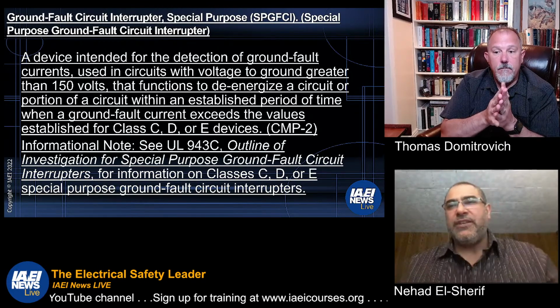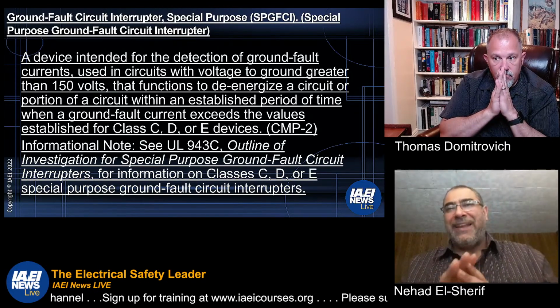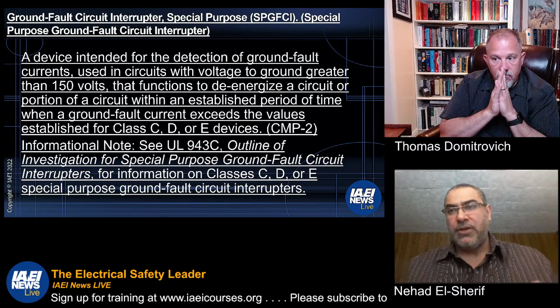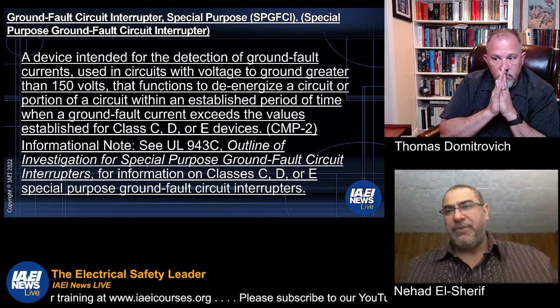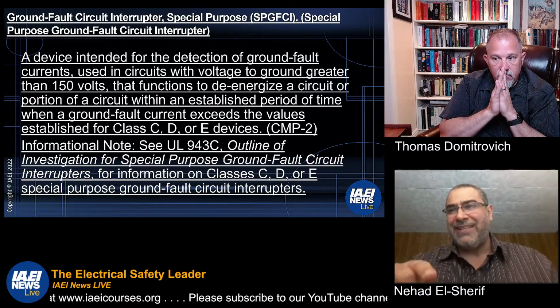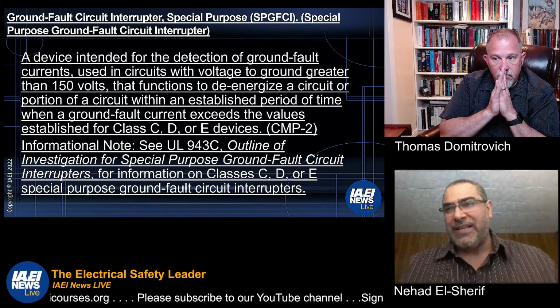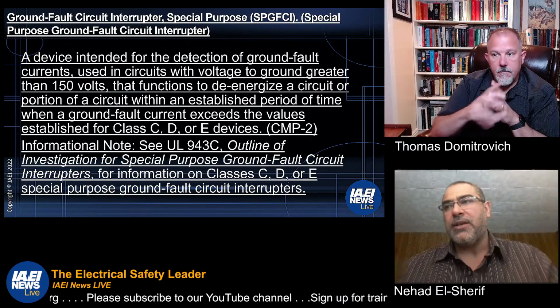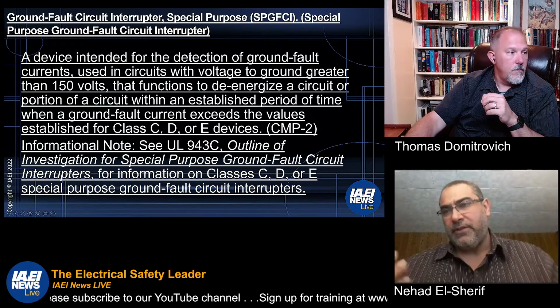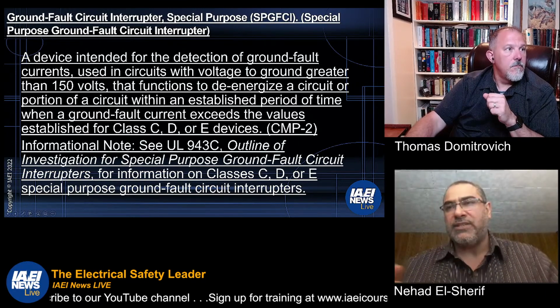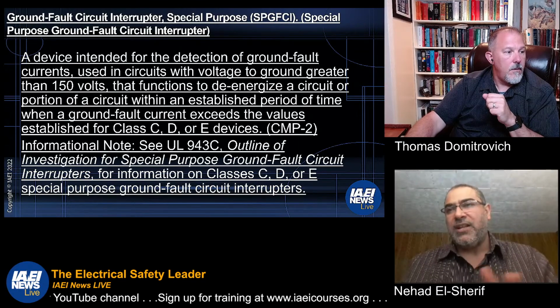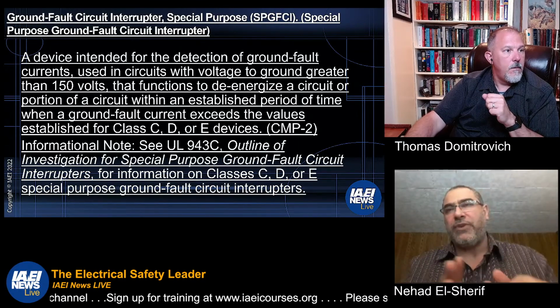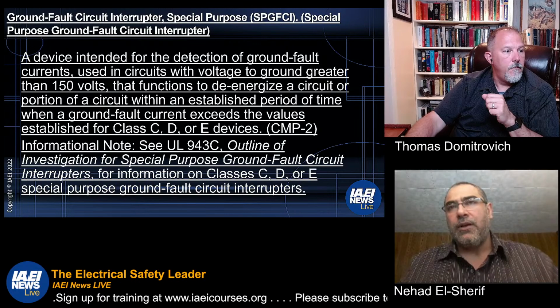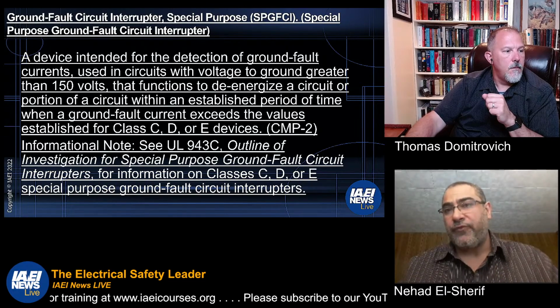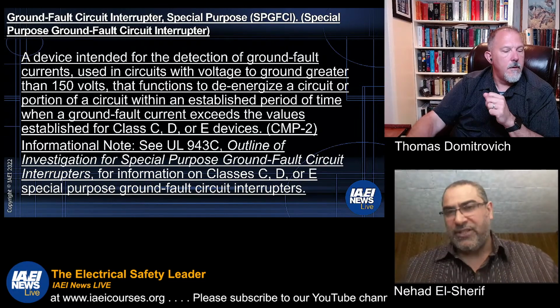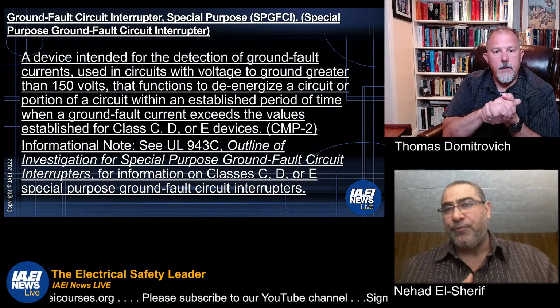And this is the first difference. When I said that any application for a Class A can be used for a special purpose GFCI, the differences come in the details, like voltage. At home, for example, you can't use a Class C or Class D because what we use at home is 120 volts to ground, and this is 150 or higher. So this is the first distinction between the two: we have a higher voltage to ground tolerance for the special purpose GFCIs, Class C, D, and E, compared to Class A.